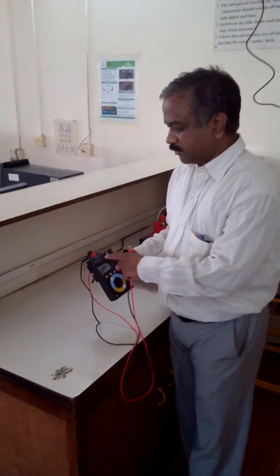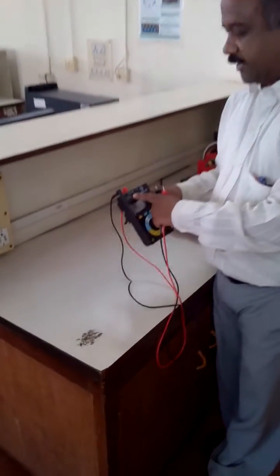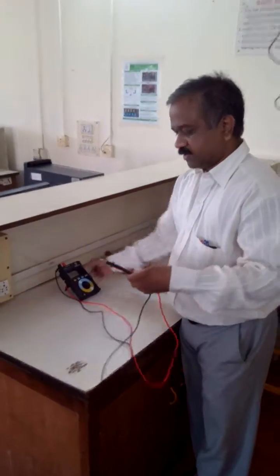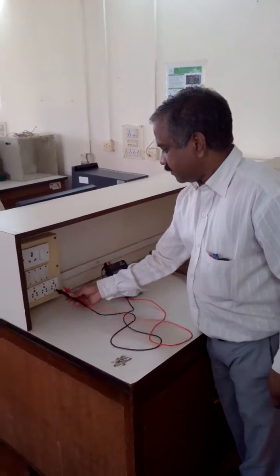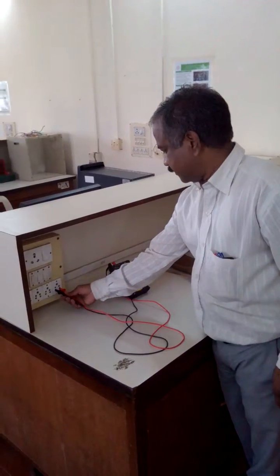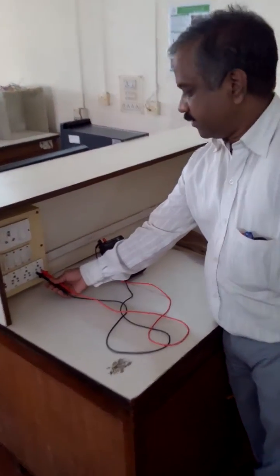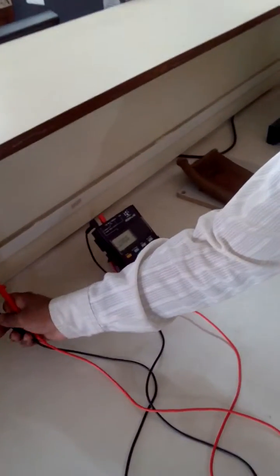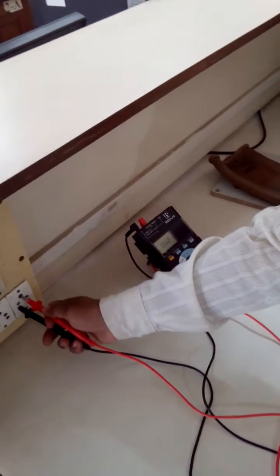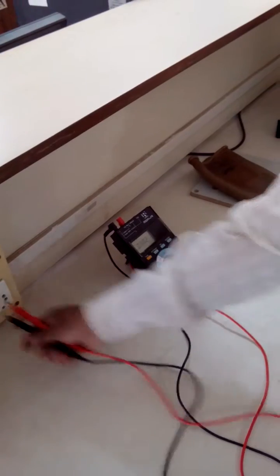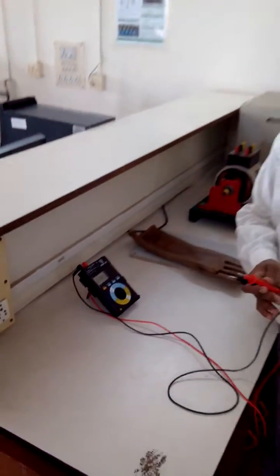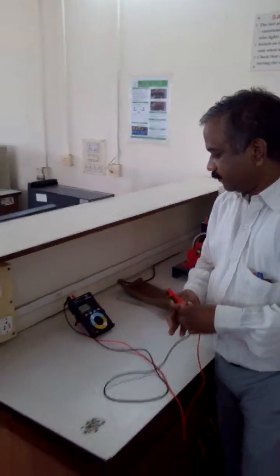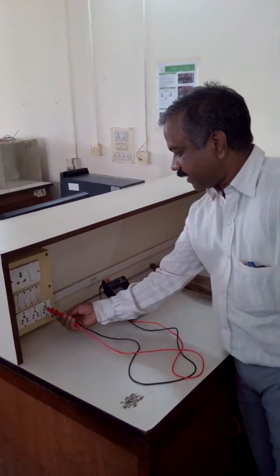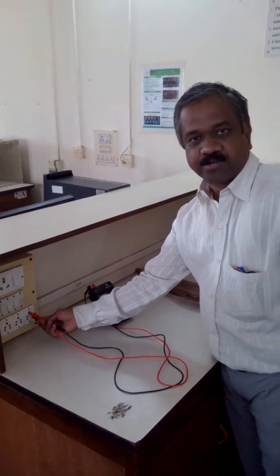So here always remember you should connect it between line and neutral, that is the phase and neutral, with the red and black wire. So here you should get 230 volt. When you connect it between earth and phase, then also you should get 230 volt. And always remember, while checking the earth connection, whether earth is properly connected or not, you should do the connection between earth and neutral.